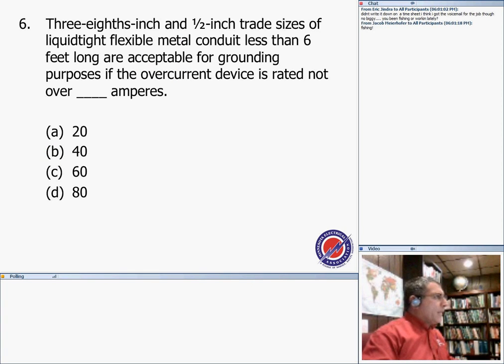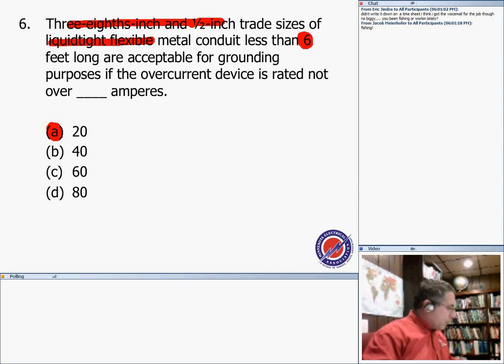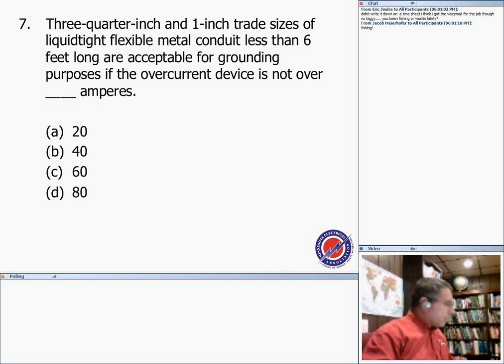Okay, 3/8 inch, and 3/4 inch and 1 inch trade sizes of liquid tight flexible conduit less than 6 feet long are acceptable for grounding purposes if the overcurrent device is, number 6, my friend, 20 amps. And this is directly, guys, with a limitation on the size and the length. So up to 20 amps, you can use it as an equipment grounding conductor if there is no flexibility or vibration coming out of the equipment. Otherwise, you have to pull an equipment grounding conductor.